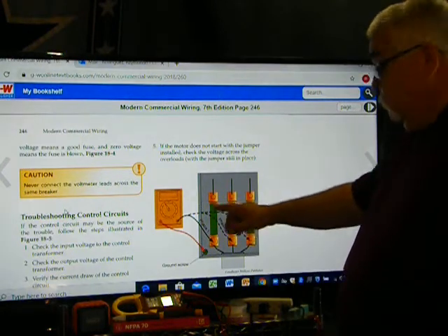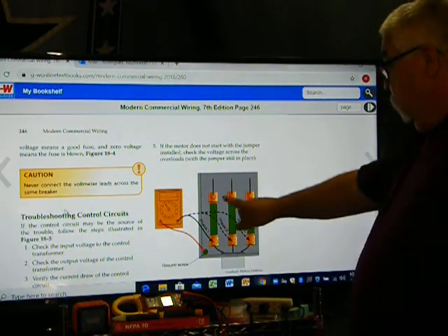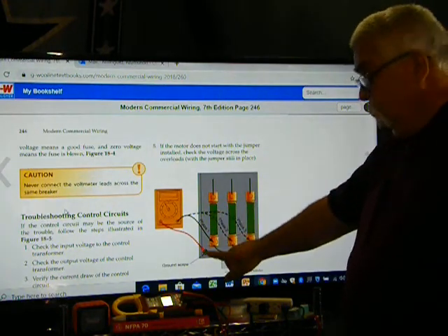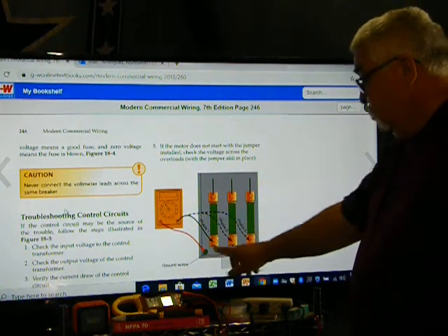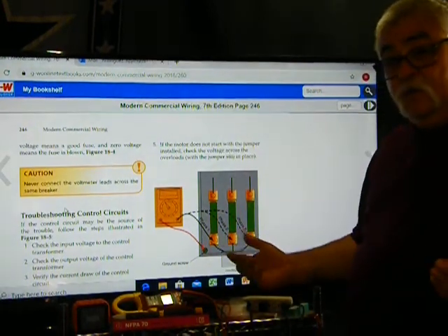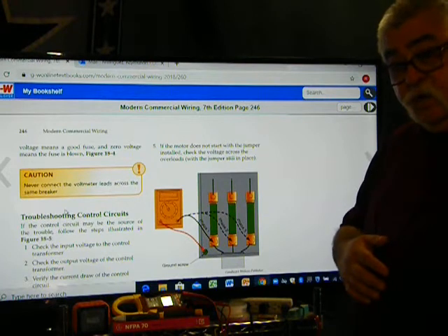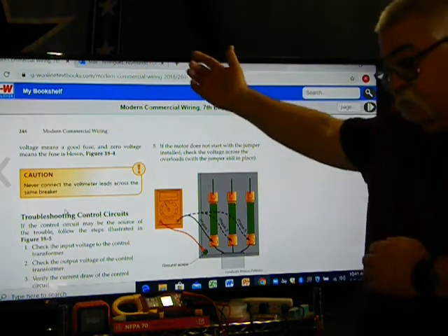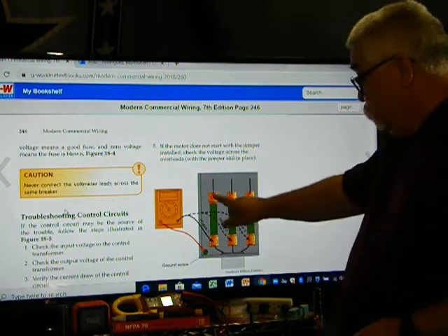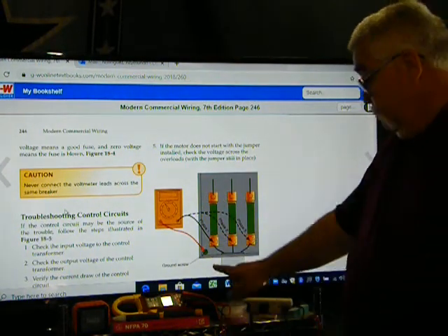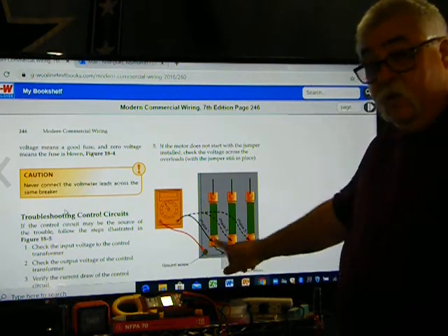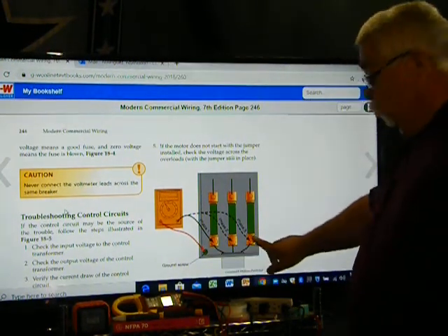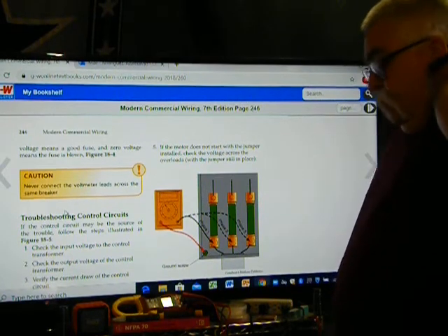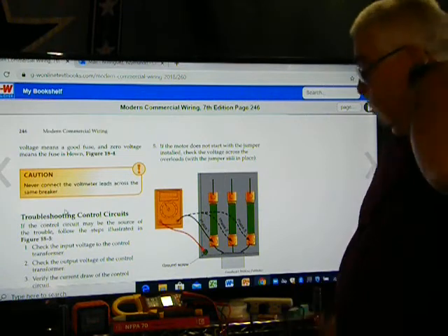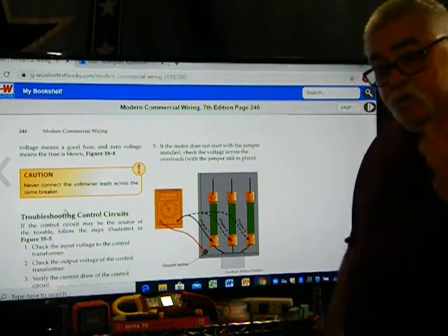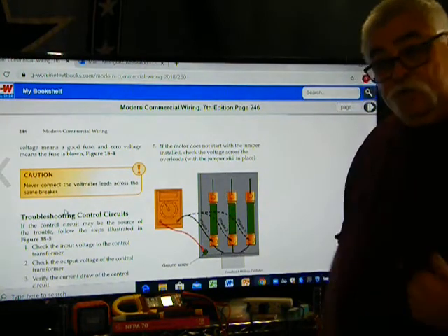So when you want to check, if I got a 120/208 and, let's say, it's 118 to ground, 118 to ground, 120 to ground, it's all within limits. Why? Because we said each one can be down to 111 and up to 129, 7.5%. But if I measure and this one is 118, that one's 105, and then this one is 120, so A and C are within the limits, but B is too low.